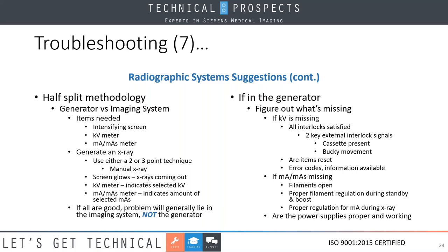Error codes. Is the information available? Error codes is something I want to spend a couple of seconds on, just to give you some key things. Back in the olden days, there were lists of X-ray error codes floating around everywhere. Everyone wanted copies of them. In today's day and age, you have an event log or error code log in your service mode. A lot of this stuff is now online. What manufacturers are doing is controlling the level of access through service keys. So you need to be in the service mode to access the error codes.